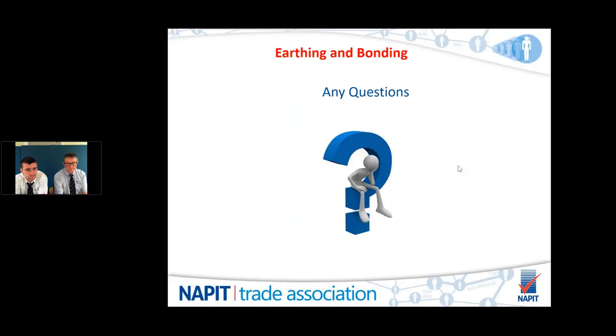Great. So going back to those polls again, we've got one from Michael asking, please advise what is the recommendation for a suspended floor such as that you'd find in a computer room? It's the same as a suspended ceiling, yeah. It doesn't need to be earthed or bonded. If you've got electrical equipment and electrical ducting and trunking going underneath the floor, then obviously that will be earthed, and it will earth the floor automatically, but the floor itself doesn't need to be bonded. Great.